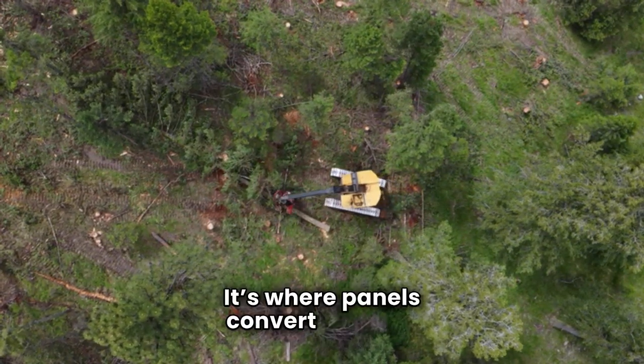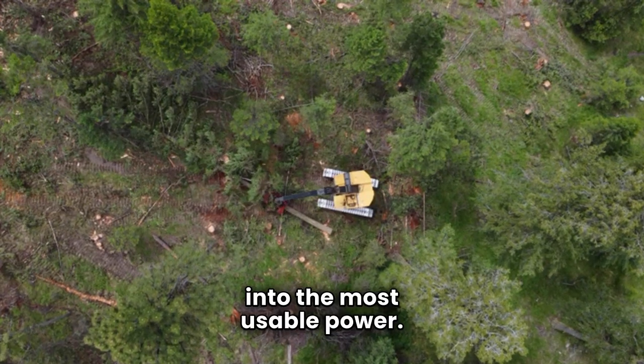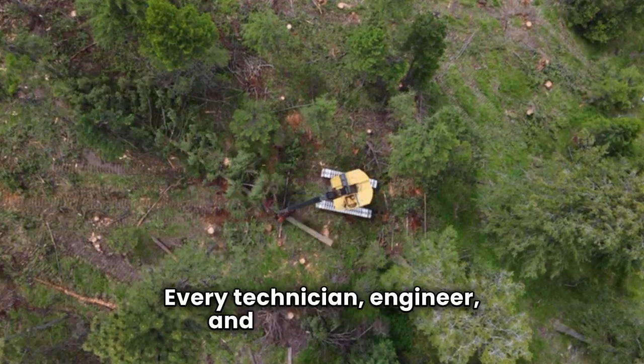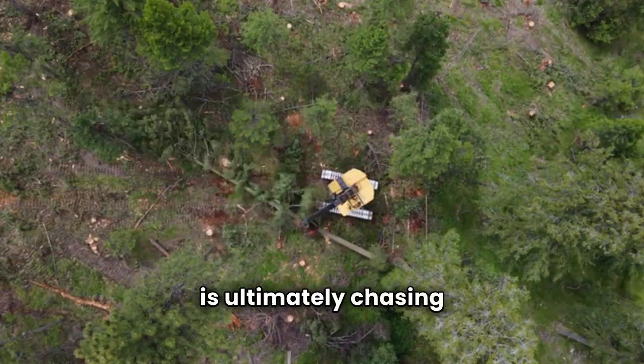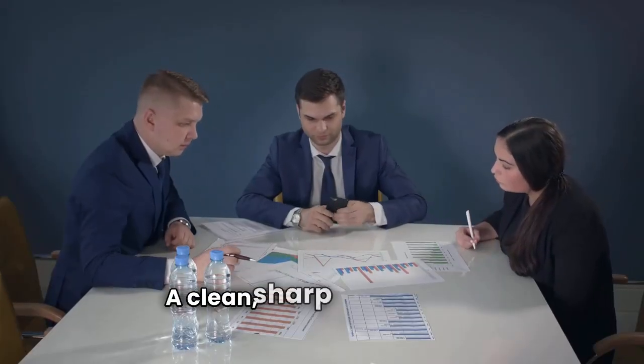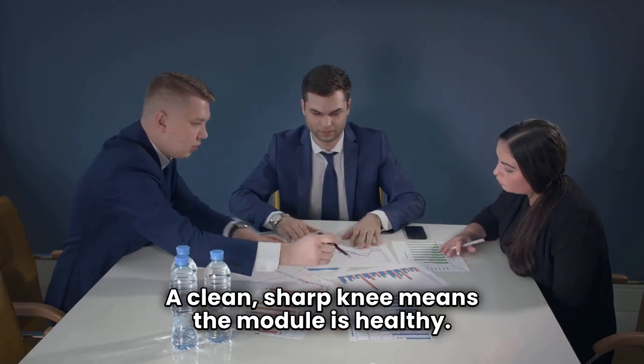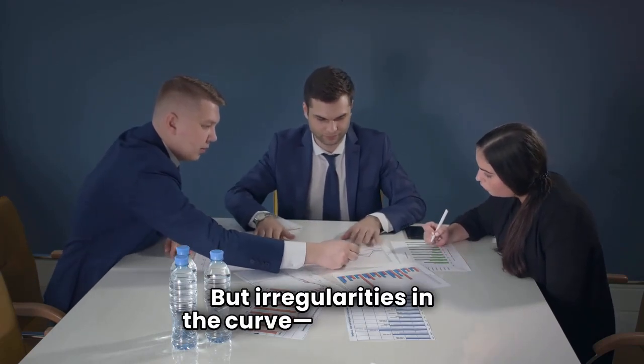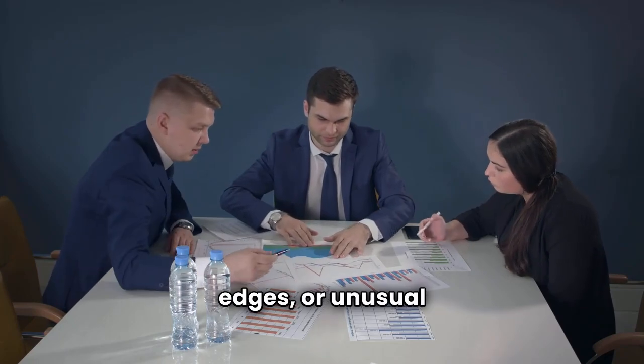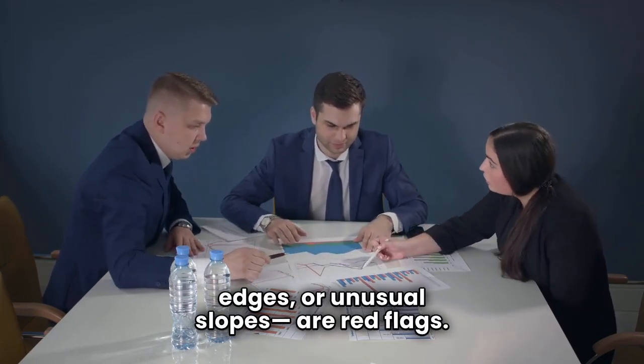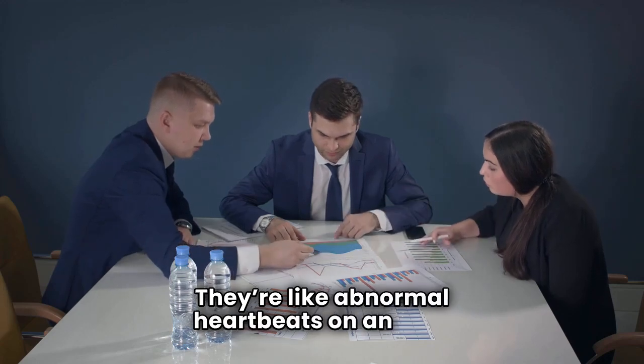That sharp knee is the sweet spot of solar performance. It's where panels convert sunlight into the most usable power. Every technician, engineer, and asset manager is ultimately chasing that sweet spot. A clean, sharp knee means the module is healthy, but irregularities in the curve, dips, jagged edges, or unusual slopes, are red flags. They're like abnormal heartbeats on an ECG.